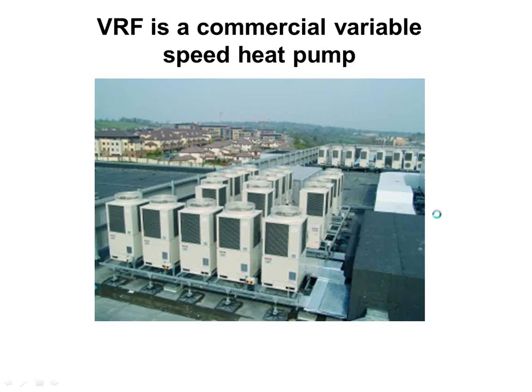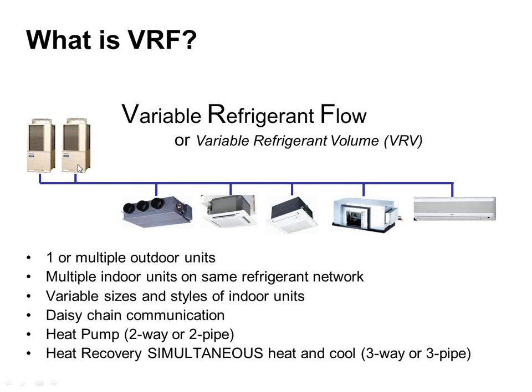And they're providing refrigerant down a main central piping system that provides cooling or heating refrigerant to all the indoor units. You can have different indoor unit types. You can have ducted units. You can have ceiling cassettes. You can have high wall duct-free split tile style units. But make no mistake, these are all heat pumps. When the reversing valve flips, the outdoor unit becomes an evaporator. The indoor units become condensers. Some of them are even sold and marketed as heat pumps.